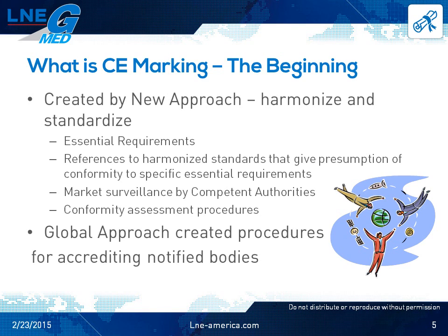So, before the New Approach Directives came out, medical device manufacturers had to apply individually to each country, satisfy each country's requirements separately for all the different European countries. The New Approach Directives, however, harmonized and standardized the essential requirements for devices, references to harmonized standards that give a presumption of conformity to specific essential requirements, how competent authorities survey the market, and conformity assessment procedures.